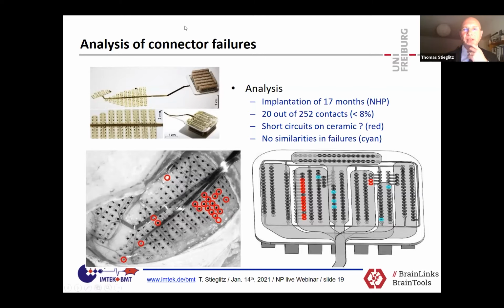And this array here of 252 contacts has seen a non-human primate for about 17 months, and it worked well. And at the end of those 17 months, less than 8% of the channels dropped out, 20 out of 252, and they were not really gone, but their signal looked like the signal on the neighboring pin. And then we thought, well, where does it come from? And we traced that back to the connector array and found out that this is a complete line here on one pin that has gone.